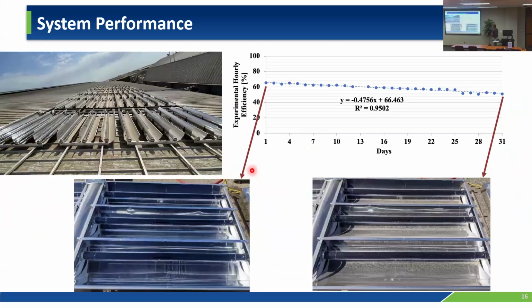We tried to figure out why it jumps suddenly every month or so, and the main reason was clean versus dirty collectors. This efficiency plot, for June or July, starts around 65% and decreases to 55%. We found that efficiency decreases by about 0.5% per day due to soiling. This shows the collectors very clean at first, then by the end of the month a lot of soiling and dust. So one of the most important points with a solar thermal system is that you need to regularly clean it to keep efficiency as high as possible.